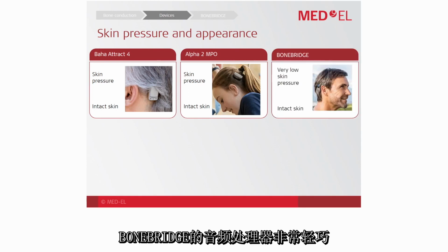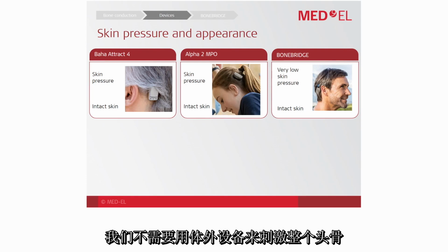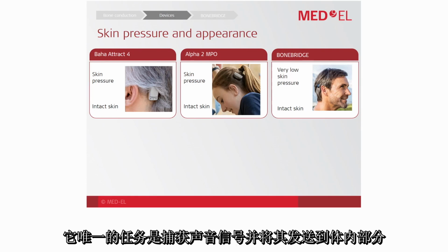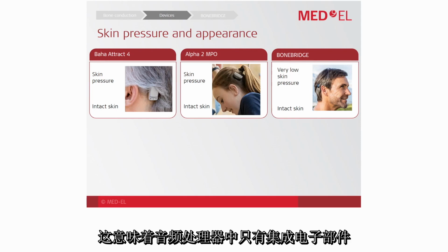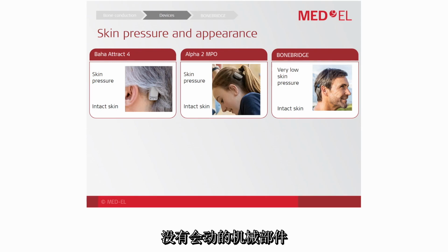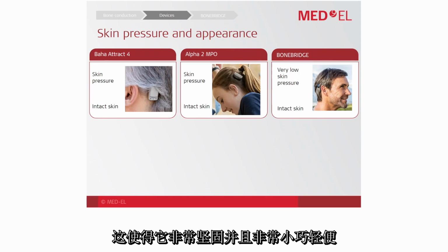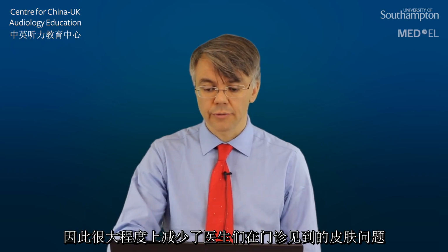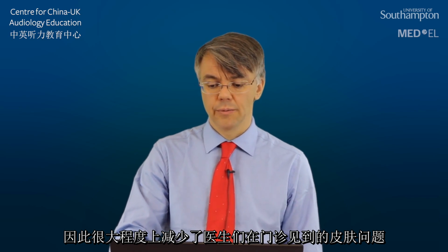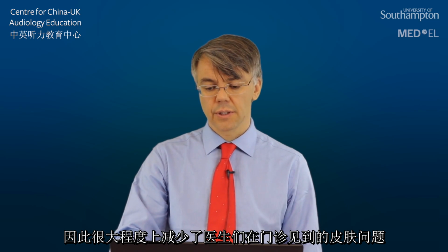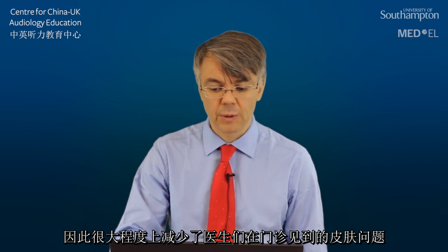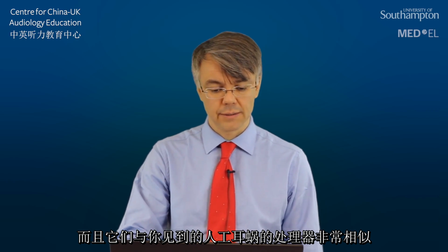The Bonebridge audio processor is extremely light. We don't need to stimulate the whole skull with the external device. The only task the device has is to capture sound signal and send it to the internal part. That means that there are only electronic parts integrated into the audio processor. There are no mechanical parts which move, which make it, of course, very robust and very small and light. And therefore, the skin problems which surgeons and experts have seen in the clinics are extremely reduced, and they're very similar to the ones you see for cochlear implants.